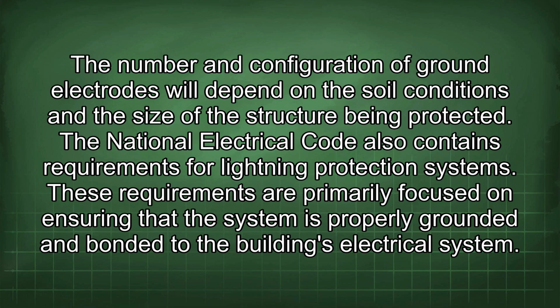The number and configuration of ground electrodes will depend on the soil conditions and the size of the structure being protected. The National Electrical Code also contains requirements for lightning protection systems. These requirements are primarily focused on ensuring that the system is properly grounded and bonded to the building's electrical system.